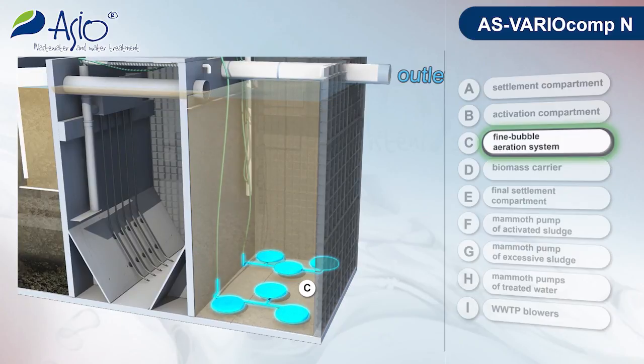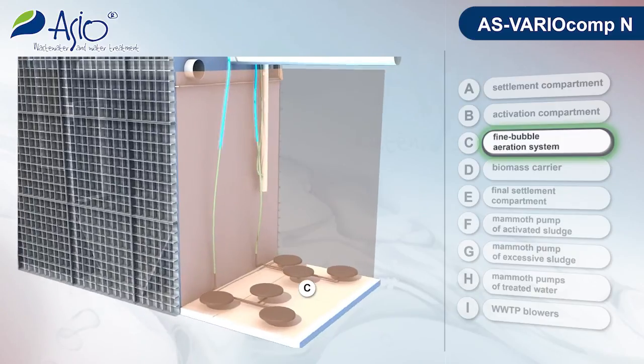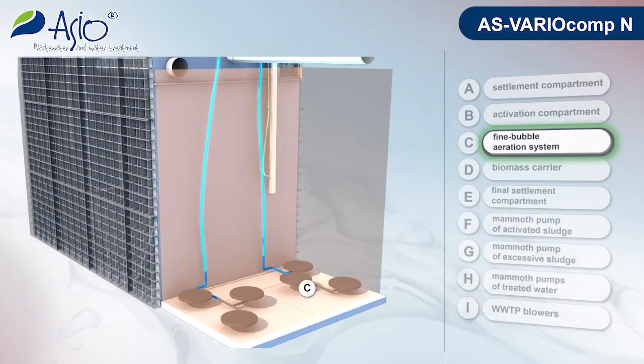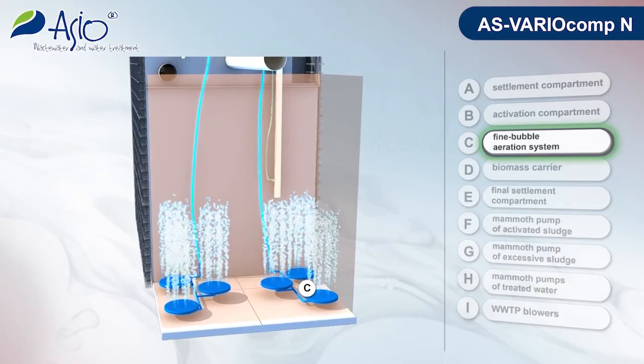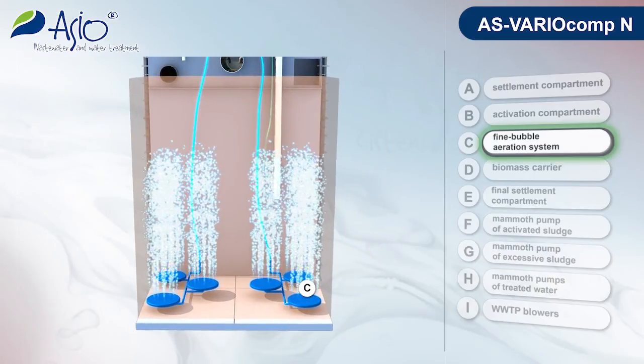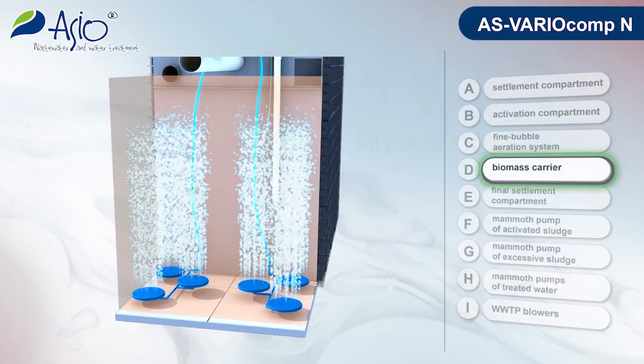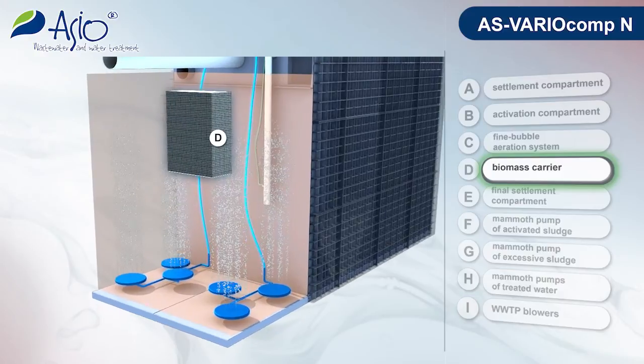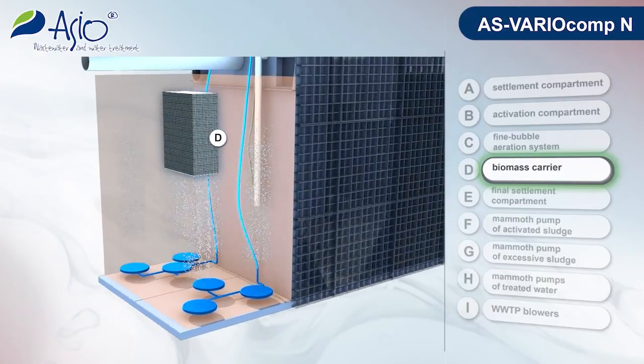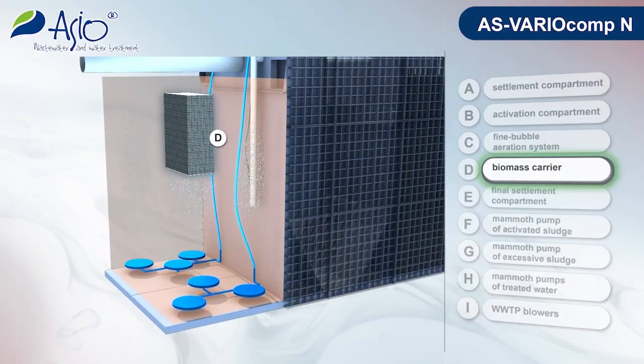In its bottom part, this space is fitted with a fine bubble aeration system into which air is fed by means of a blower, and possibly with a biomass carrier to improve the stability of the process of an overloaded or minimally loaded plant.